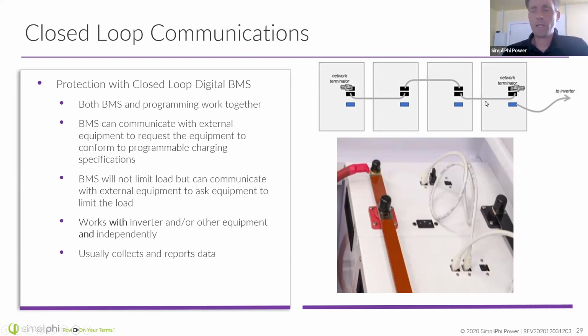The other thing to note is that only one of the batteries of the chain needs to be connected with communicating equipment. So for instance, if you were installing one of our ESS systems with our communicating batteries, you would install one cable coming out of one battery and go to our gateway. If you have a communicating inverter like a Sol-Ark, you only need to connect one of the device ports of the battery to the inverter. So there are battery ports on each battery, these two, and then there's a different port that's labeled device on each of the batteries. And that device port goes to the communicating equipment like a charge controller or an inverter.